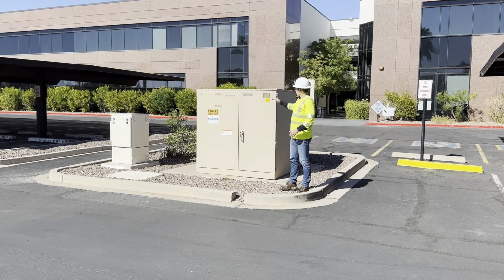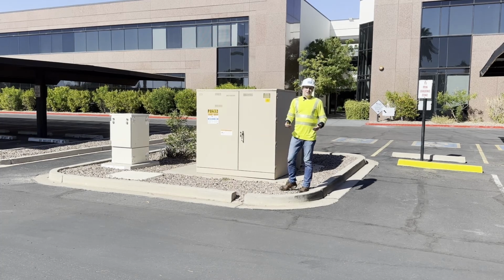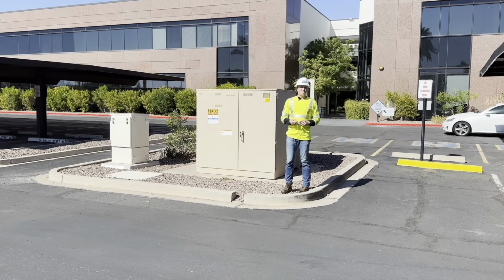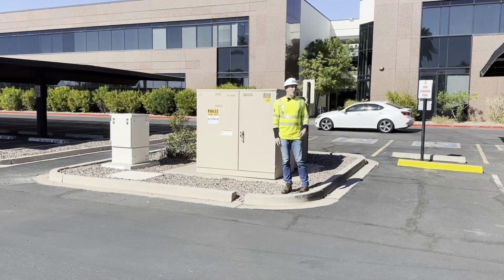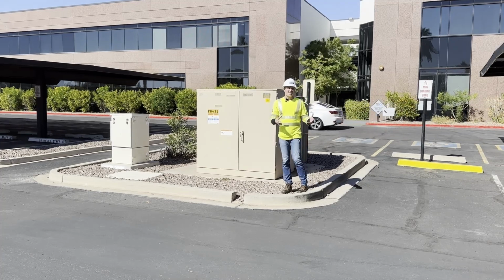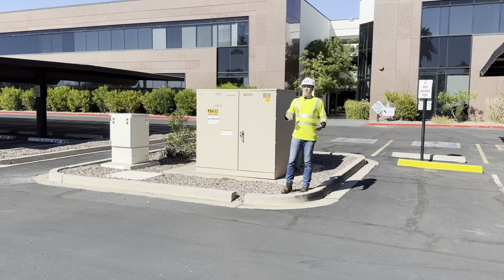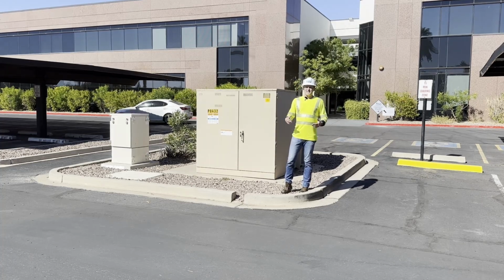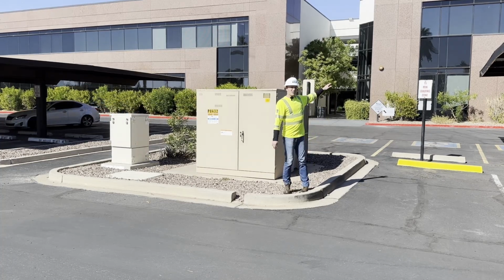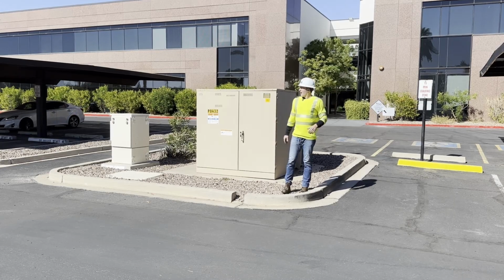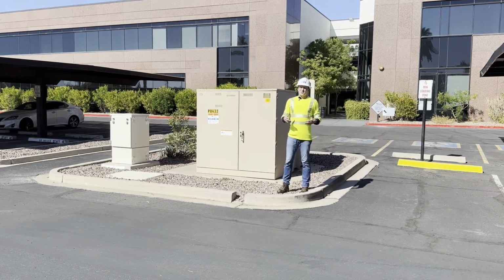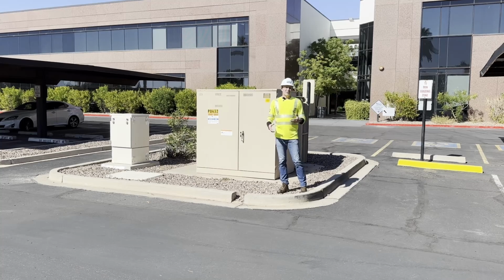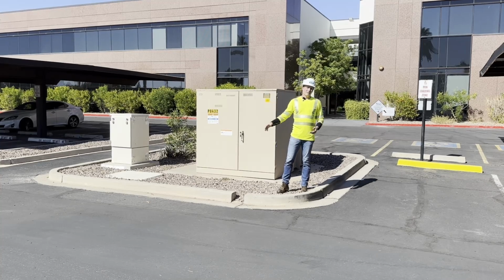So the three voltages that we generally find in North America are 120/240 split phase - that's what's going to your home or a small business or a small gas station. You have 120/208 three phase, which you'd have for a complex like this, for example. Or you have 277/480, which is what we're mainly going to be using when we're building DC fast charging projects - we need that 480 volt power to power our DC fast chargers.